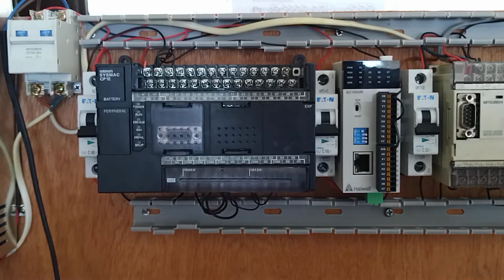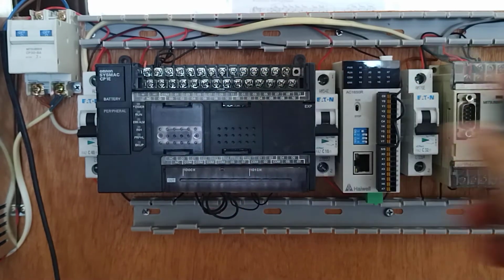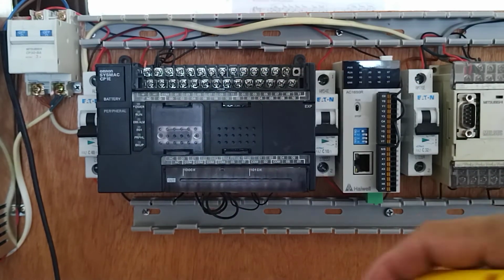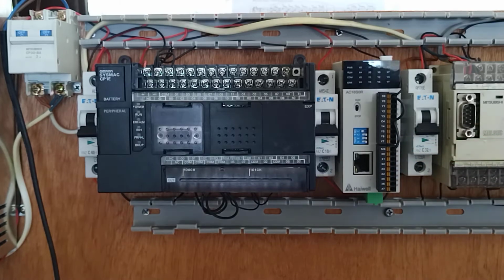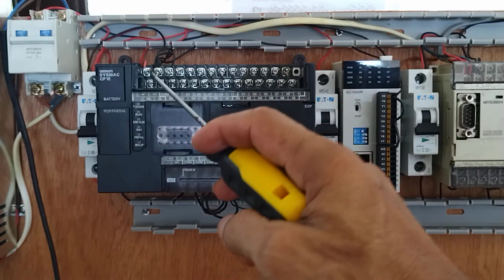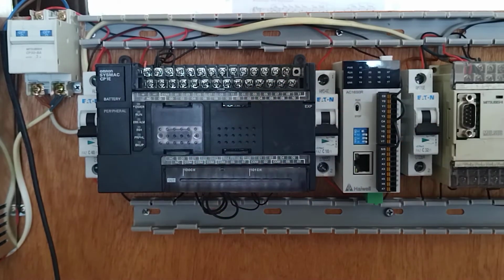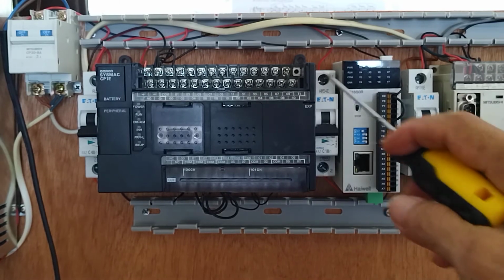So power supply is the most important thing. Then the next part is how you are going to wire your PLC—understand how the digital inputs and digital outputs are to be wired in your PLC. There are some things you need to consider, so that will be the next part of this tutorial. But what's important here is providing the proper power source to each PLC: this one is 220, this one is 24 volts, and this one is 24 volts.